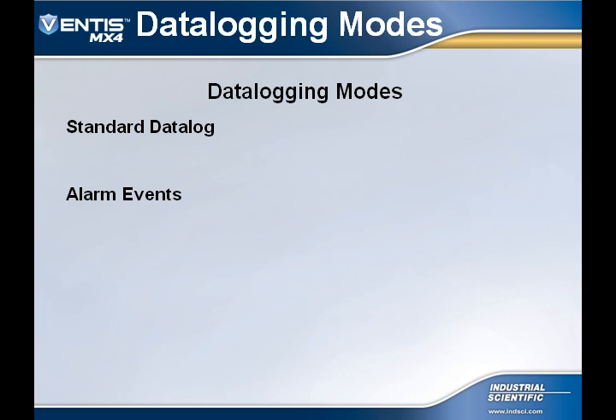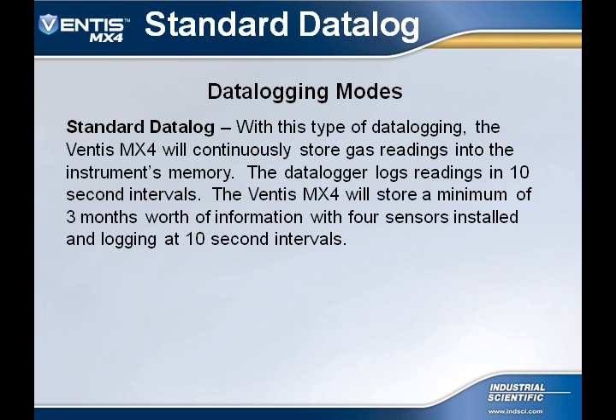The Ventis MX4 has two data logging modes: the standard data log and the alarm event data log. With the standard data log, the Ventis MX4 performs data logging at 10-second intervals and can hold approximately 3 months of data for a 4-sensor configuration. Readings are time-stamped and stored in a first-in, first-out FIFO queue that is overwritten when full.